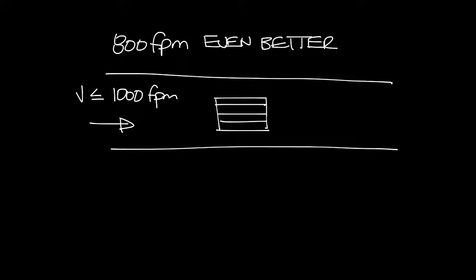The second rule of thumb is that the static pressure of the grill you mount on the ductwork should have a pressure loss of more than 1.4 times the velocity pressure in the duct.